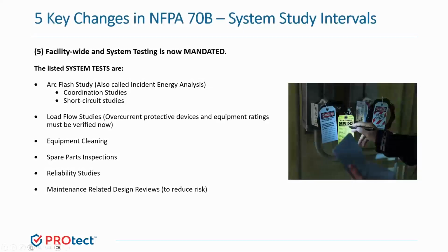Yeah, so the final key change relates to more testing, specifically entire facility and system testing. There are system studies outlined in NEC, NFPA 70E, and now NFPA 70B that provide detailed requirements for system studies. For all types of studies named below, the mandatory minimum period, so the interval between studies, shall not exceed 5 years. So that's going to include your short circuit analysis, your coordination studies, and incident energy analysis.